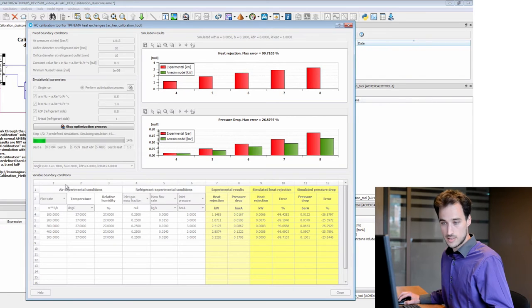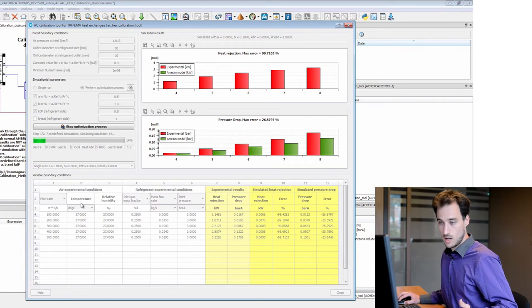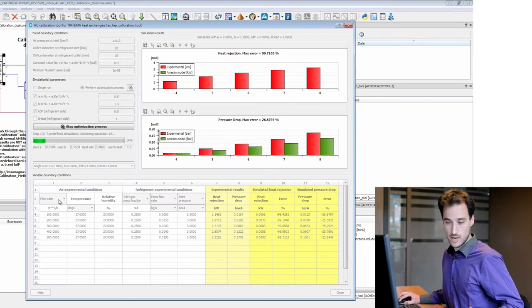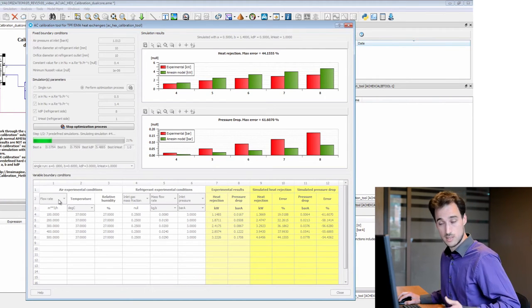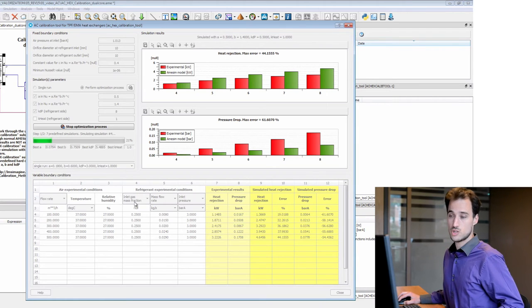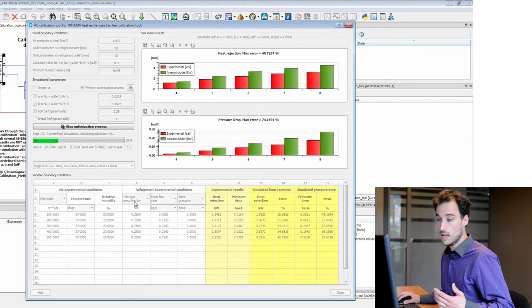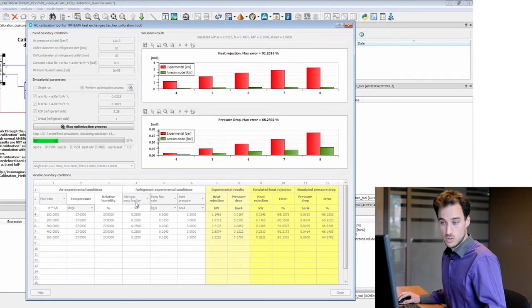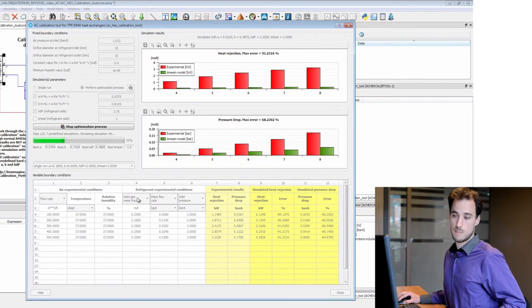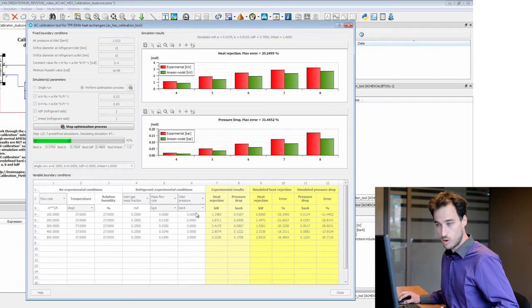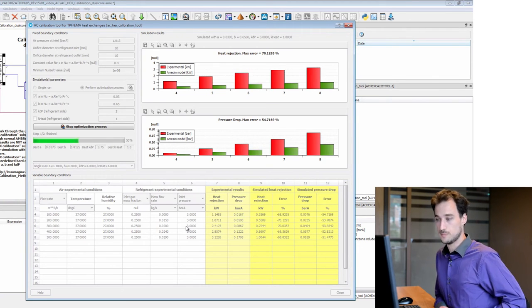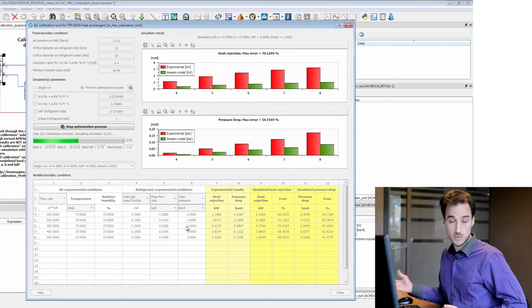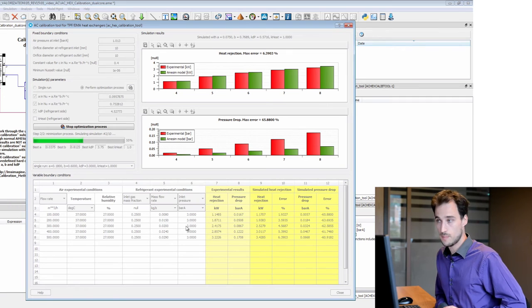First is that the conditions here, the boundary conditions can be set with various things. For example, for the air condition you can set either flow rate or velocity. For refrigerant inlet conditions you can set temperature, superheat, subcooling, and here considering an evaporator, obviously inlet gas mass fraction is the best setting. So there are several settings that can help you set your data with respect to supplier data very easily in this tool.